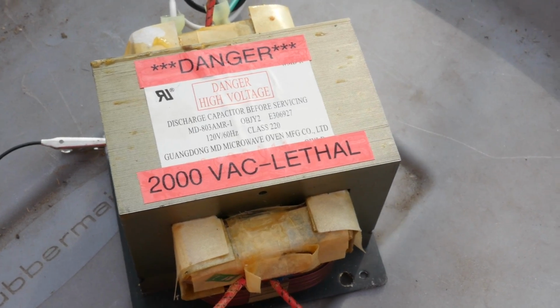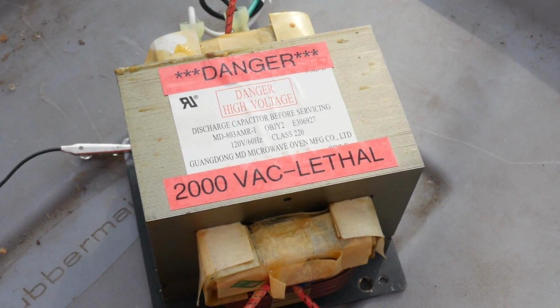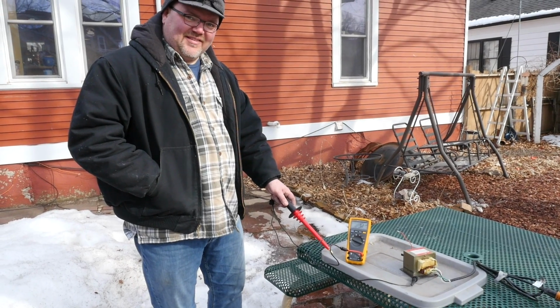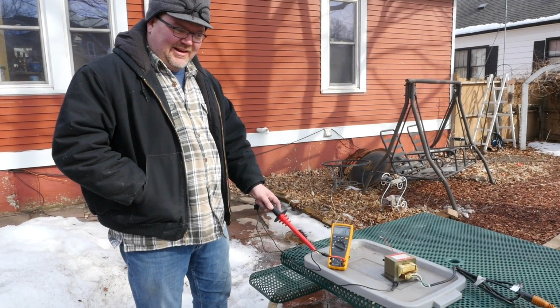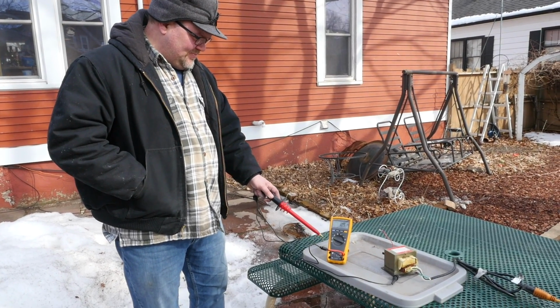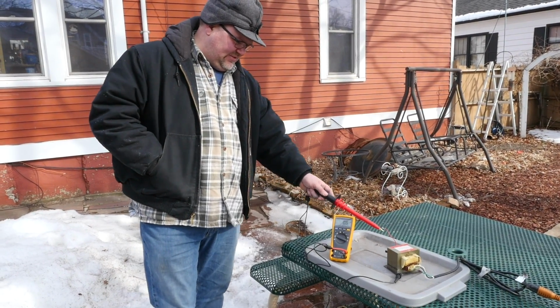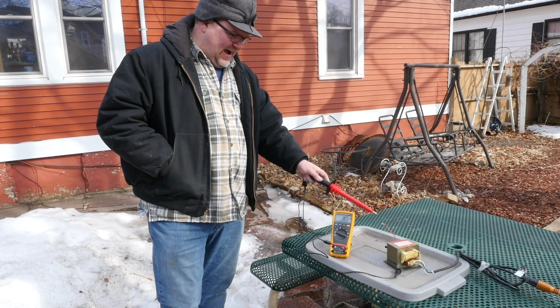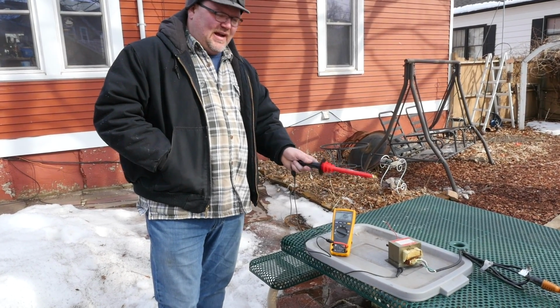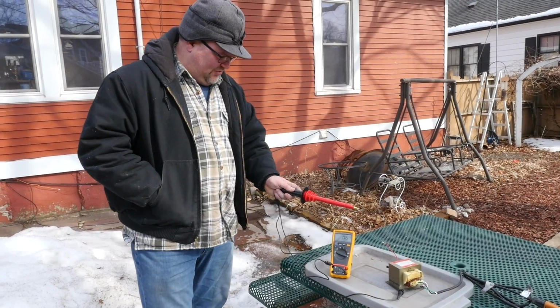Now, for you safety freaks, I understand the fine Rubbermaid cover here is not rated for 2,000 volts, so we need to understand that. We're going to make sure that this secondary lead here does not come in contact with anything else. It's pretty short, so we shouldn't have too many problems.